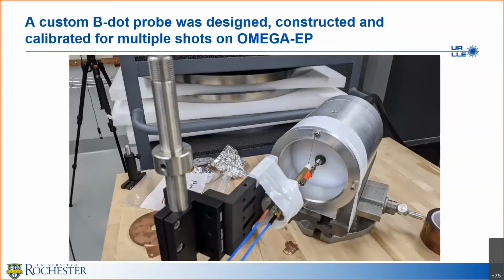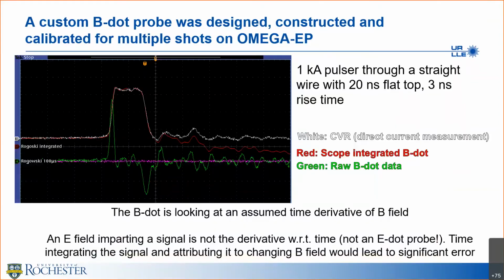And we tested this in the lab. We have a little pulse power device that pulses about a 20 nanosecond pulse with a 3 nanosecond rise with a kiloamp current. We can actually move the pulser around back and forth. It's on a stage relative to the probe, and we can verify the probe and its functionality and calibrate it. So here's an example of one of those calibrations.